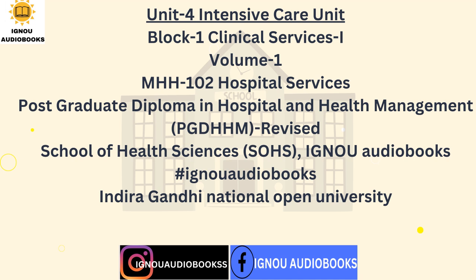Apart from these, it is also recommended by various authorities that there should be facilities for instant measurement of acid base and oxygen tension in arterial blood by an electrometric technique and a modified Clark's electrode, available in the adjacent laboratory area where a spirometer test also can be carried out.